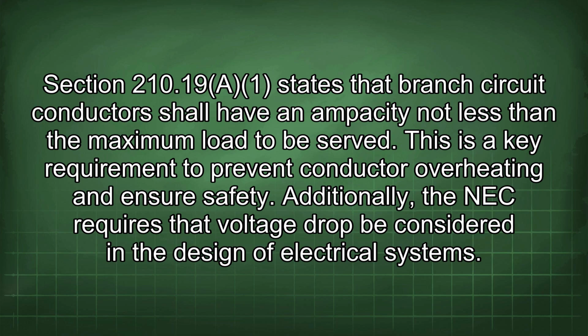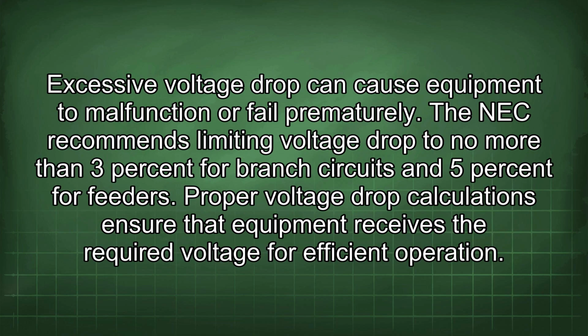Additionally, the NEC requires that voltage drop be considered in the design of electrical systems. Excessive voltage drop can cause equipment to malfunction or fail prematurely. The NEC recommends limiting voltage drop to no more than 3% for branch circuits and 5% for feeders. Proper voltage drop calculations ensure that equipment receives the required voltage for efficient operation.